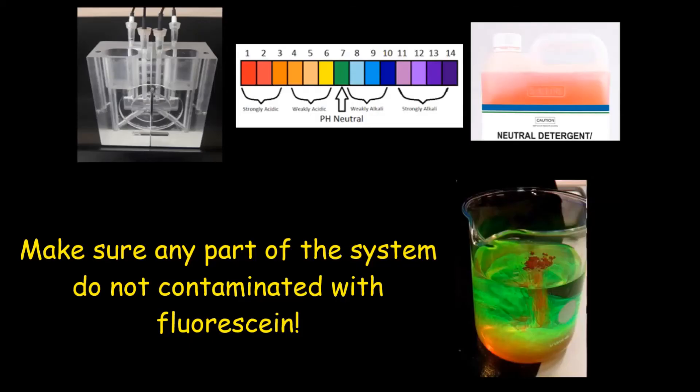The chambers should be cleaned with neutral detergents. Make sure no part of the system is contaminated with fluorescein after the cleaning.